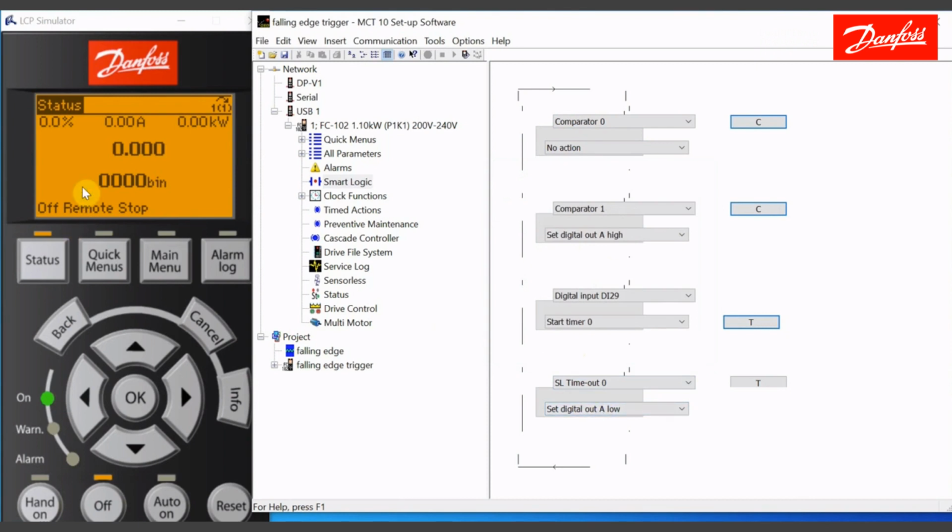So I have in my display the digital outputs. I still have terminal 53 here. So once I dial that above 5 volts, it gets to that second step of the sequence where it's looking for it to go less than 4.5. These are the digital outputs. This character represents terminal 29. So when I go below 4.5 volts, that should activate for a second, which it does.